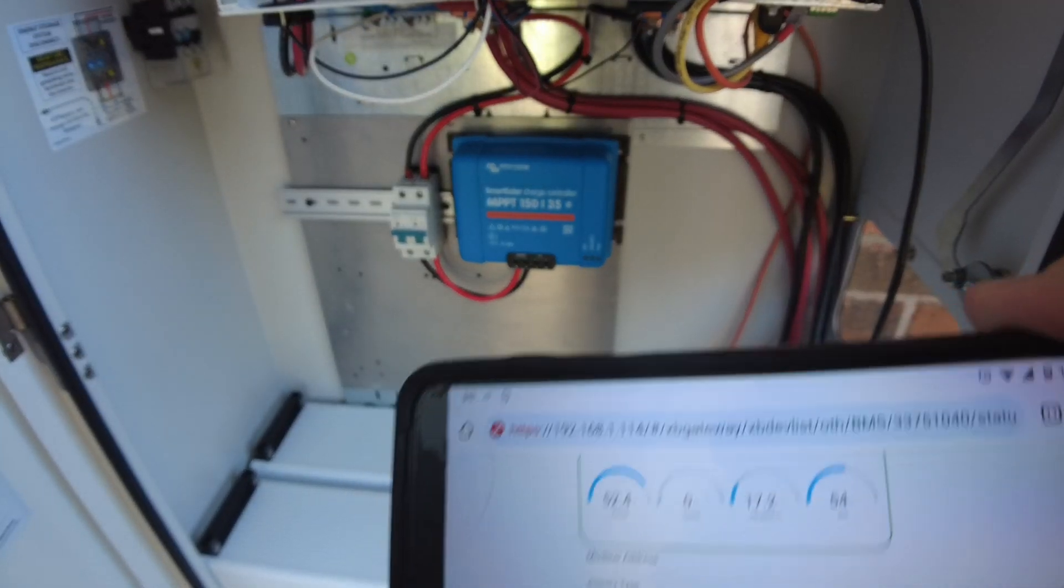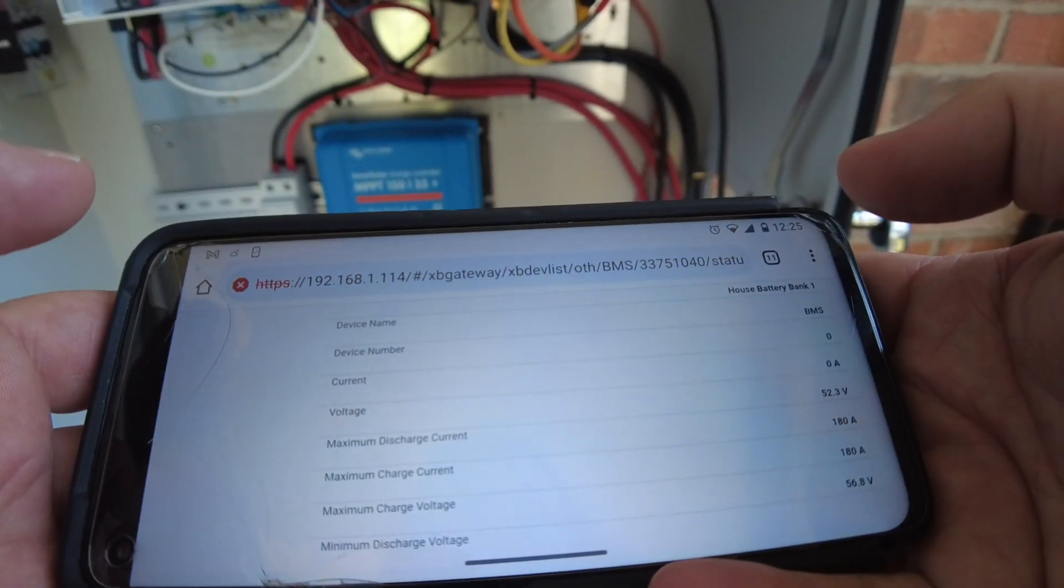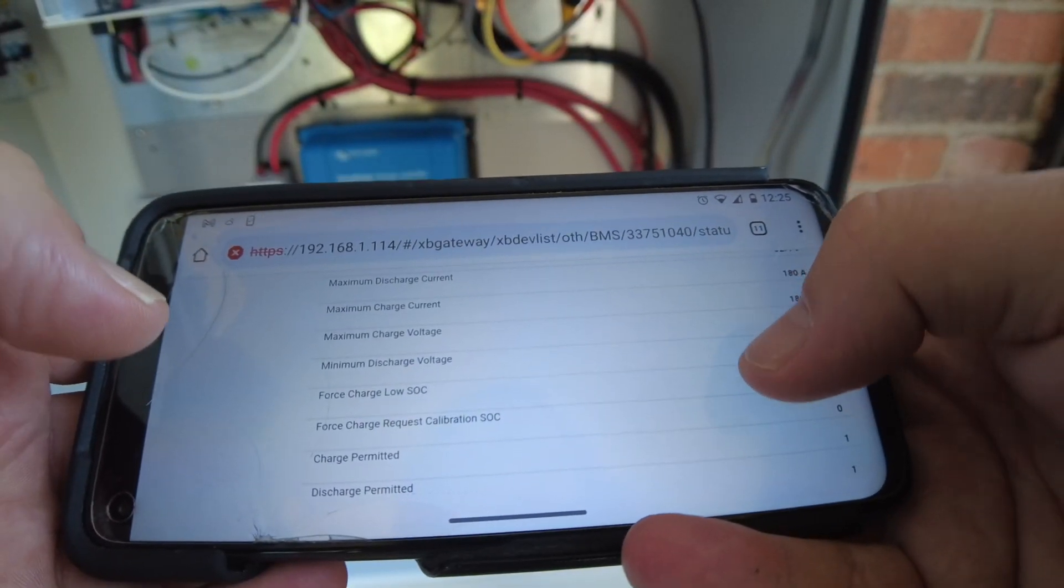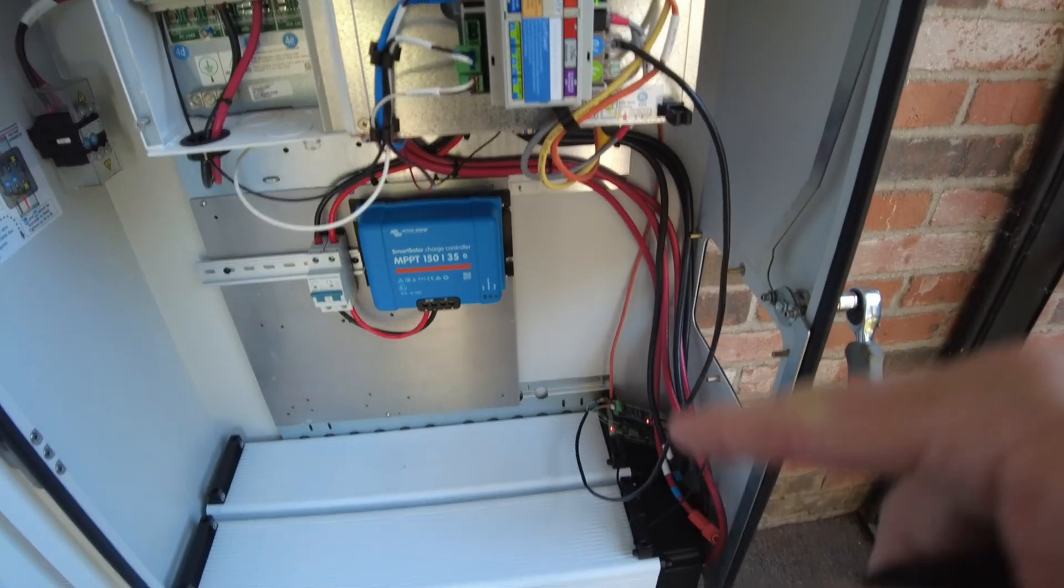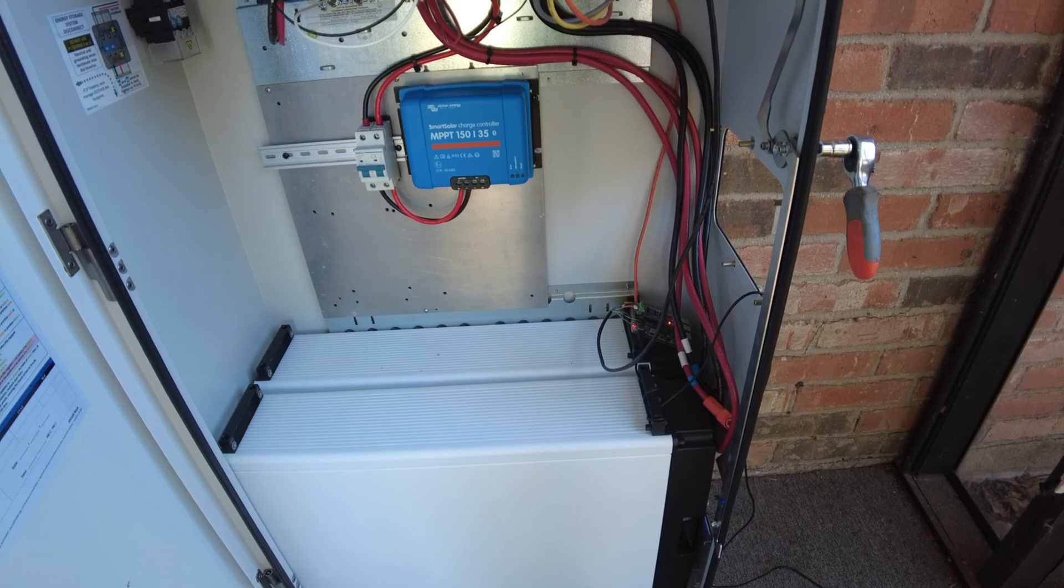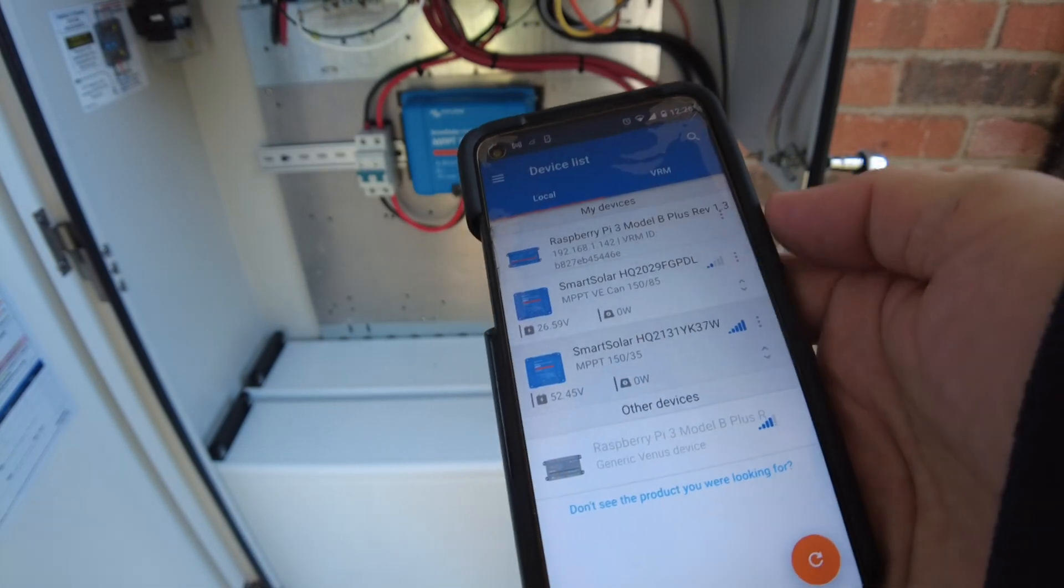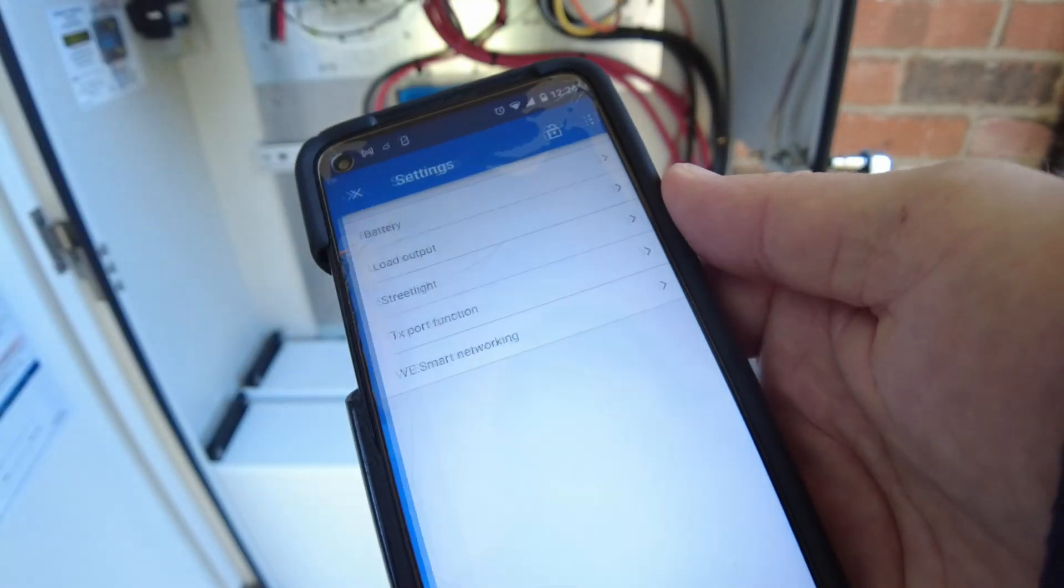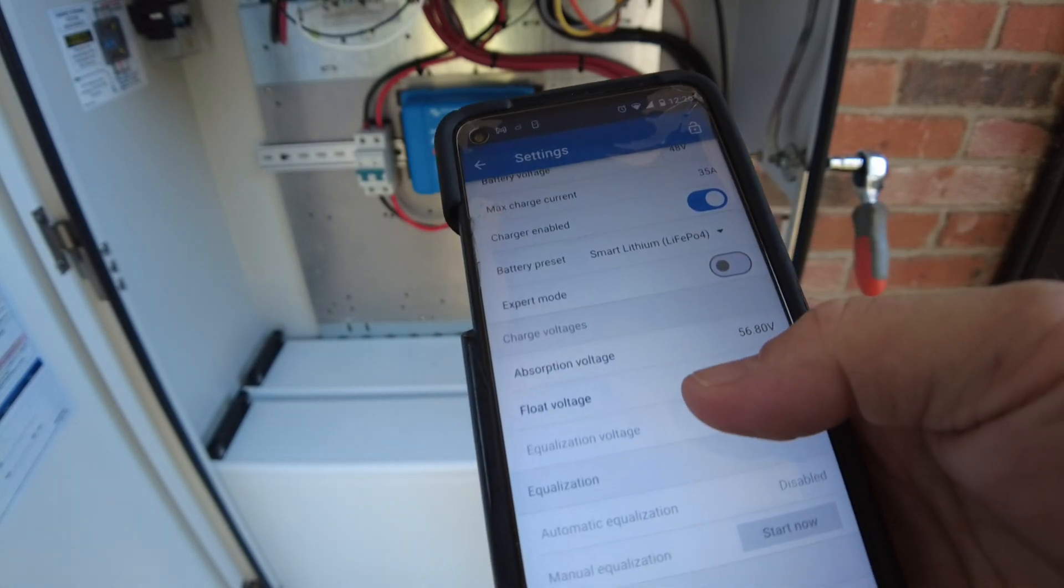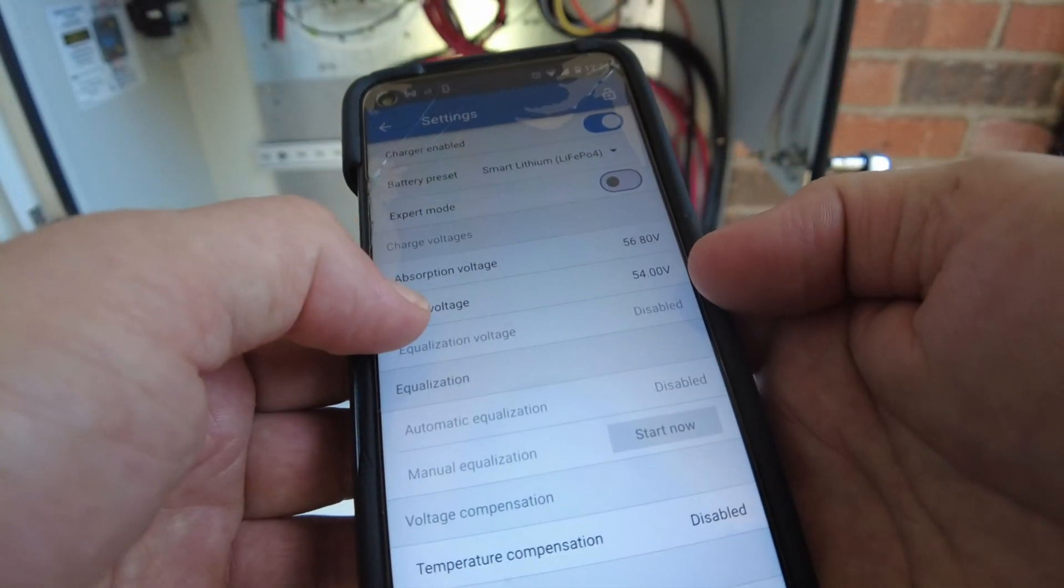So I'm logged into the gateway right here, and this is telling me the specs on the battery. What we're looking for here is the maximum charge voltage—it says 56.8 volts, so these batteries want to be charged to a maximum of 56.8. Let's go into the Victron app and we'll connect to the 150/35. Let's check out the battery settings. Okay, we're already set at 56.8, so we are good. It'll float at 54.